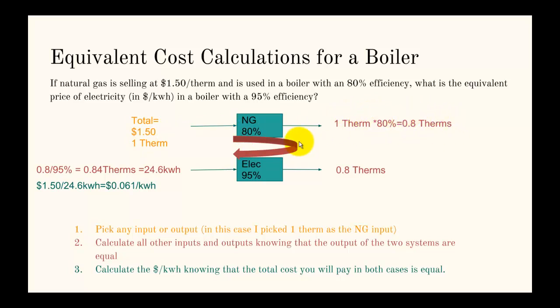We take this one therm and calculate the output of the natural gas boiler. Because we know the efficiency and we know the input, we can calculate it using input times efficiency equals output. So we get 0.8 therms. Since these are serving the same space, it's an equivalent price, we know that the output has to be the same.